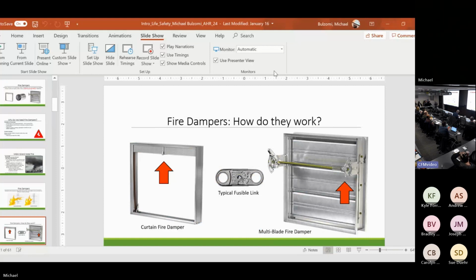Code difference: if I'm the building code, I cannot tell the difference between these two dampers. They're both rated to UL 555. They both have an hourly protection rating. They both meet NFPA requirements. It's a cost issue.